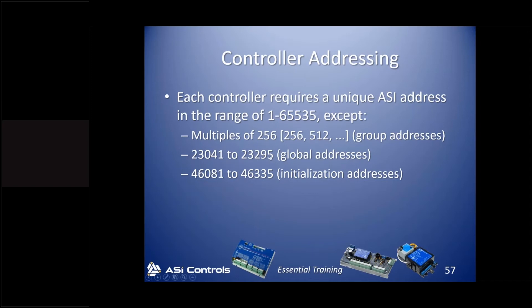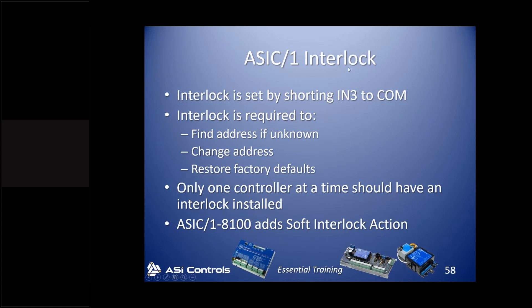There are addresses in the 23,000 range reserved for what we call global addresses — to make a change affecting all controllers of a certain type. There are also addresses in the 46,000 range reserved as initialization addresses, used for certain housekeeping tasks mainly in ASIC/1 controllers. The primary initialization address is used with what we call an interlock, which is set by shorting Input 3 to common — either at the controller or through our MicroSync device, which is a USB-powered temporary communication interface.